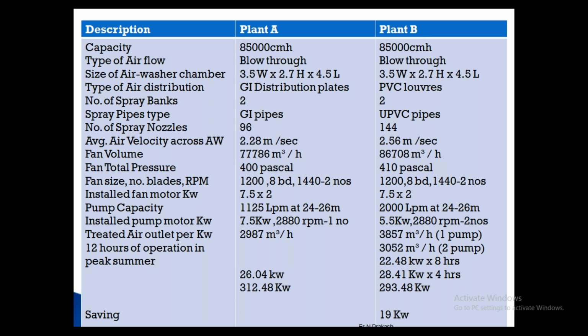The fan size was 1200, both fans are 8 blade fans, two numbers, and the installed fan motor was 7.5 kW. The pump capacity was a single pump of 1125 liters per minute, installed earlier with 24-26 meter head. Whereas we installed 2000 liters of pump capacity, two pumps, each of 5.5 kW, instead of a 7.5 kW single pump.